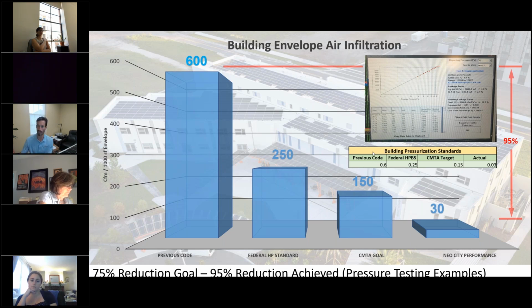This shows that there was a previous code that mandated 0.6 CFM per square foot at 75 Pascal. So basically what that means is the building is allowed to have 600 square foot of open leaking airspace in 1,000 square foot of envelope. And so what we've said is, okay, if we can minimize that down, but then over ventilate using the dedicated outside air system, we can increase the ventilation rate, but pull it through a filter, pull it through energy recovery, go through dehumidification, and improve the learning space in the educational space.